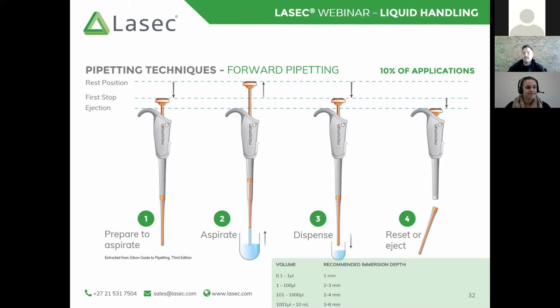Much the same as an air displacement pipette, you'll prepare for your aspiration by going to the first stop. Unlike an air displacement pipette, you can now physically see the movement of your plunger, so it is a better telltale sign. You can visually confirm that that piston is reaching the end of the tip, so you are ready to aspirate. Again, you would do this step before placing it in the solution.